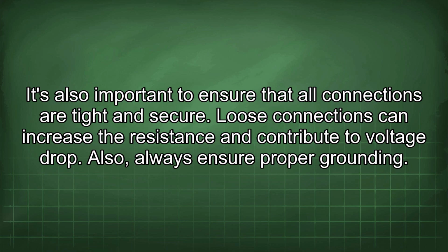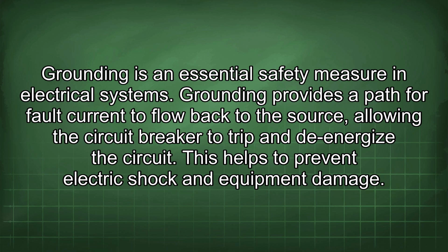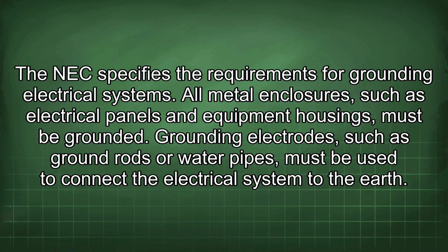Also, always ensure proper grounding. Grounding is an essential safety measure in electrical systems. Grounding provides a path for fault current to flow back to the source, allowing the circuit breaker to trip and de-energize the circuit. This helps to prevent electric shock and equipment damage. The NEC specifies the requirements for grounding electrical systems. All metal enclosures, such as electrical panels and equipment housings, must be grounded. Grounding electrodes, such as ground rods or water pipes, must be used to connect the electrical system to the earth.